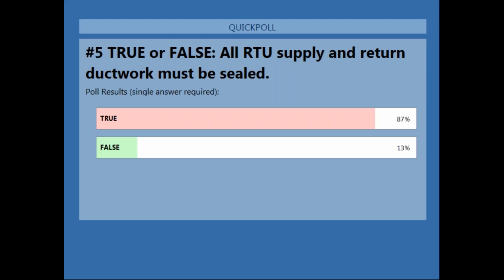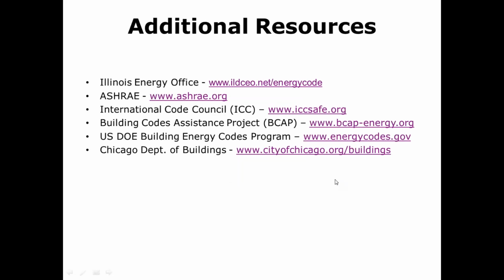All ductwork on rooftops or any other ductwork must be sealed. All of it has to be sealed. You only have to test the leakage if you get above 3 inches, but all ductwork sizes need to be sealed. All right. So that is going to wrap us up unless you have further questions.